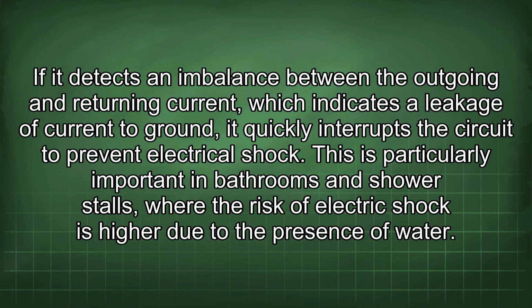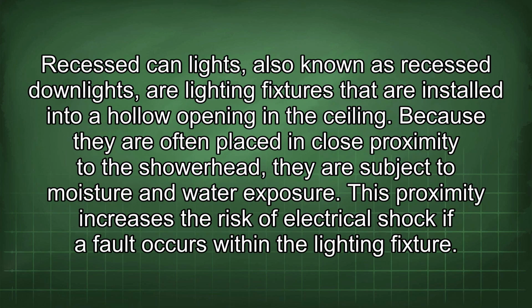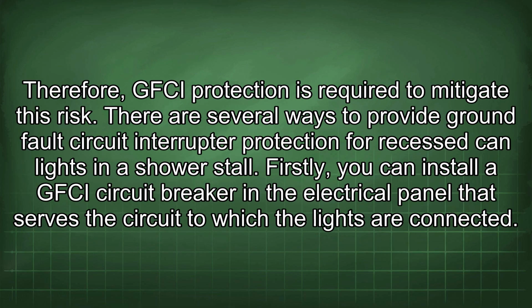presence of water. Recessed can lights, also known as recessed downlights, are lighting fixtures that are installed into a hollow opening in the ceiling. Because they are often placed in close proximity to the shower head, they are subject to moisture and water exposure. This proximity increases the risk of electrical shock if a fault occurs within the lighting fixture. Therefore, GFCI protection is required to mitigate this risk.